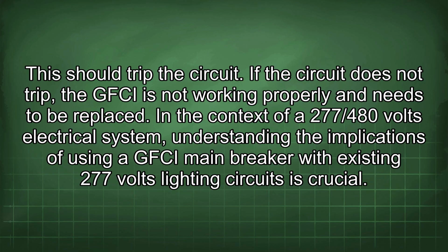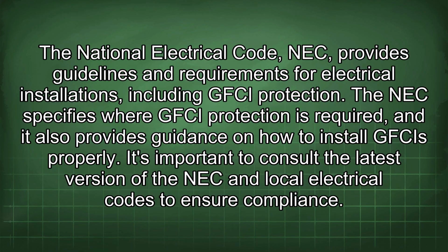In the context of a 277/480 volts electrical system, understanding the implications of using a GFCI main breaker with existing 277 volts lighting circuits is crucial. The National Electrical Code (NEC) provides guidelines and requirements for electrical installations, including GFCI protection. The NEC specifies where GFCI protection is required, and it also provides guidance on how to install GFCIs properly. It's important to consult the latest version of the NEC and local electrical codes to ensure compliance.